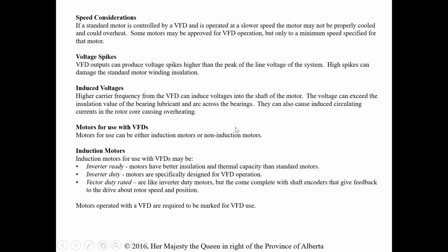So speed considerations. Again, if a standard motor is controlled by a VFD and operated at a slower speed, it may not be properly cooled. A lot of them have fans on them to cool them, so the fan's not turning as fast. They may have specific speeds, even if they are rated, that we can't exceed or go lower than, if that's their rating. So we definitely have to pay attention to that. The voltage spikes: the VFD output can produce voltage spikes higher than the peak of the line. This can damage the winding insulation on the motor itself. So again, it's rated for a certain voltage. If we put voltages that are greater than that, we can damage the motor.